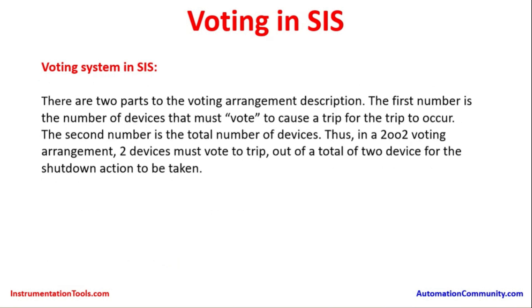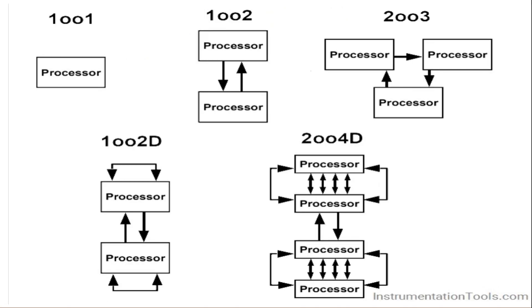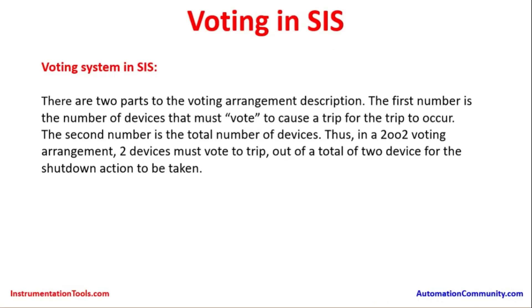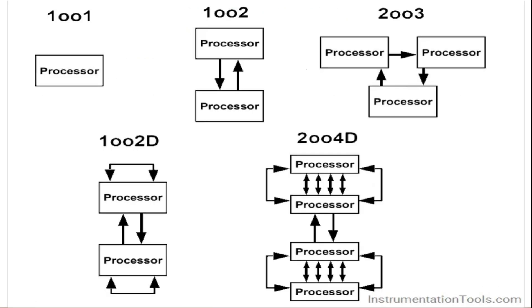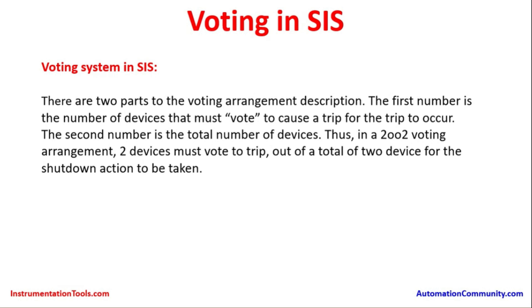In the voting system in SIS, there are two parts to the voting arrangement description. When we say 1 out of 1, 1 out of 2, or 2 out of 2, we need to understand what the first number and second number mean. The first number is the number of devices that must vote to cause a trip for the trip to occur. For example, 1 out of 2 means 1 instrument failure out of 2 instruments is required to trigger a trip.